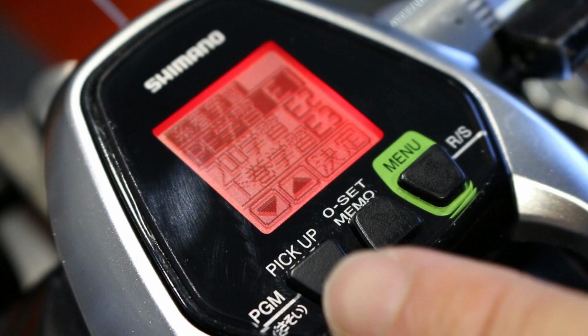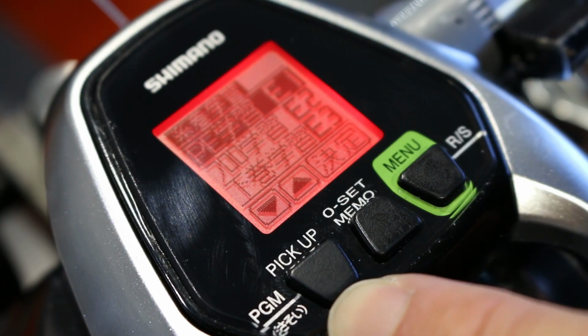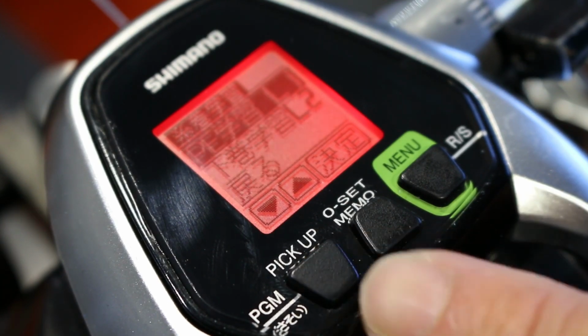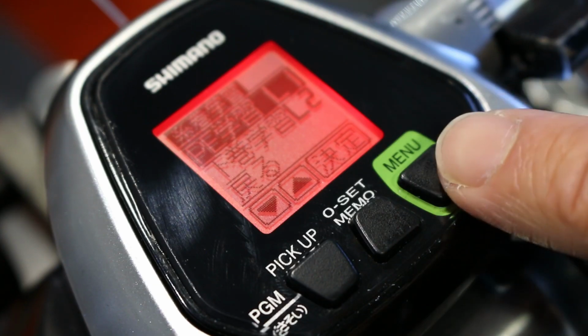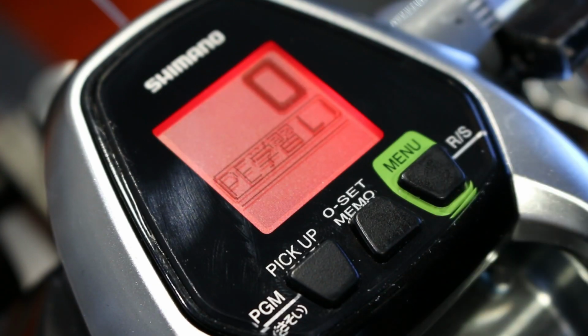Now that we're in the calibration menu, you'll see the different calibrating methods. To select L1, use the pickup button 3 times to scroll down to L1. Once you see that, push the menu button to select.